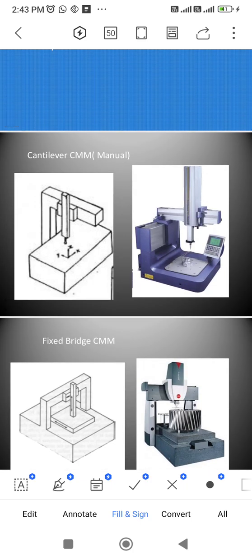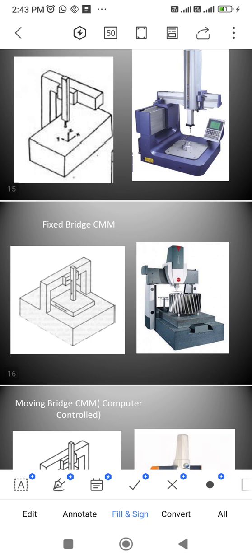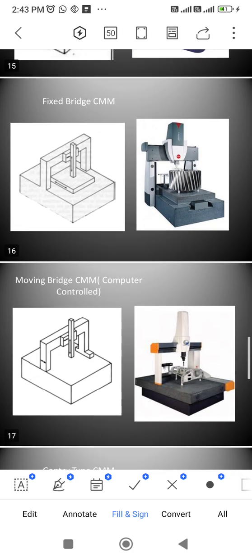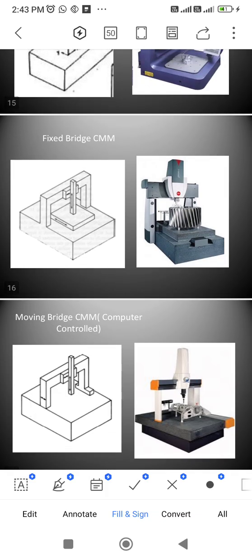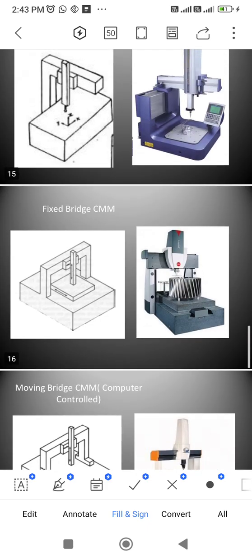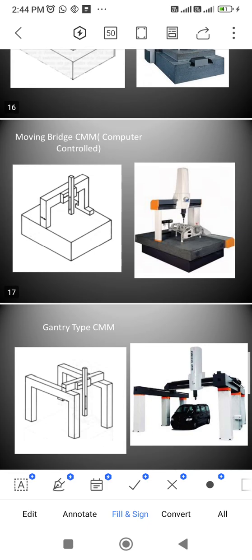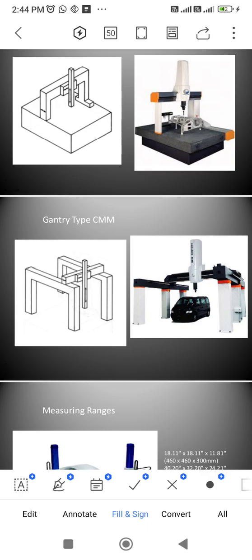So this is cantilever CMM. So we know the word cantilever. One side is fixed, another side will be free. And this is the fixed bridge CMM. So both sides of the lever are fixed. So we can call it as fixed bridge. And it is a moving bridge CMM. So commonly we can say it as bridge type CMM. So one is fixed type and another one is moving type. So in this the bridge will be moving in a moving bridge. In fixed bridge CMM the bridge is fixed. And this is the gantry type.